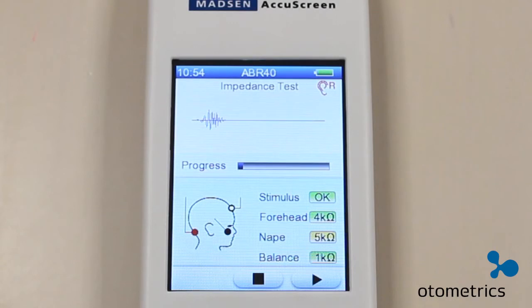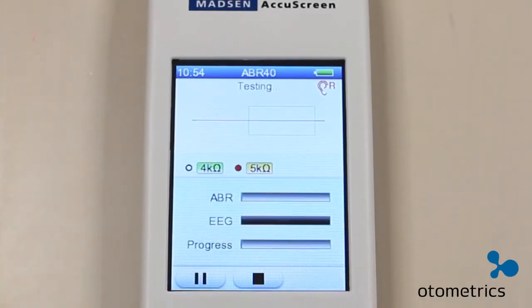Depending on how you have set up the Accuscreen and Acculink, the test will start automatically when the impedance values reach the desired levels, or you will have to press the play button manually in the lower right corner of the screen. During testing, you will see some information about the test. The ABR appears in the upper part of the screen. The green rectangle indicates the portion of the ABR that is monitored. Below the ABR, the white and red electrodes impedances are displayed.